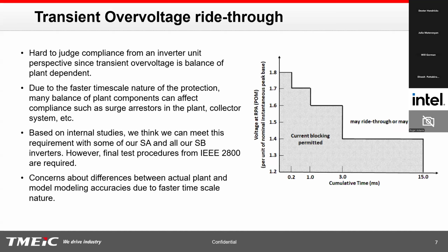We're waiting for 2800.2, the test procedures from the final standard. We did some internal studies to see if the inverter can ride through with certain protection functions. We were able to see that it is possible to ride through with appropriate protection settings, but again, we cannot say for sure until we have more guidance on this.